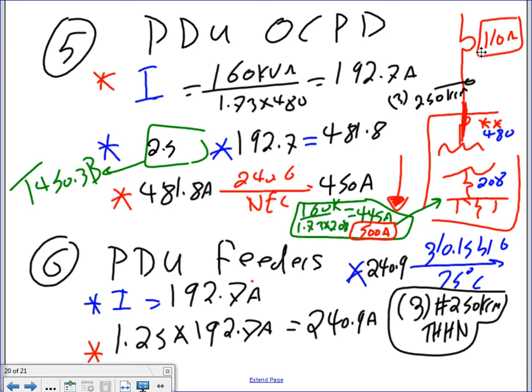So what they do, remember, the PDU is a transformer and a panel. They put the transformer in one section. Right next to it, they have a panel rated for 500 amp with 20 amp receptacle, 20 amp circuit breakers in it. I can't emphasize, guys, next week or the week after when we go to the site, you're going to be looking at these PDUs and UPSs. Now, we don't size anything for the 500 amp because these are all in one box already. Can you guys see that circuit breaker here and that bus here? It's all manufactured, a big box, or we just bring a feeder to it. But it's good to know the amps you need here because that amperage is going to be distributed. Typically they have that box and multiple panels on both sides. Here's my PDU. On this side you'll have 225 amp panel, 225 amp panel, 225 amp panel. 3 panels fed from the same transformer.